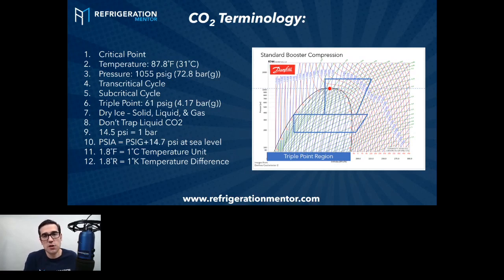In larger commercial applications there will be reliefs, and you do not ever want to trap CO2, because the temperature can rise really rapidly. If the system is designed for a high standstill pressure, then you're okay. These are just some of the things that we want to understand, because there are higher pressures and it's important to know these safety features. I talk a lot about the different units. I think this is really important. A lot of this equipment that you're seeing coming into Canada and North America comes from different countries, from Europe, from Japan.